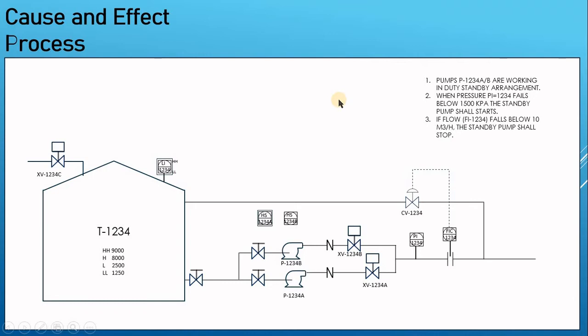We'll use this P&ID in more than one video because we'll try to add and subtract from it. The P&ID has some notes: you have a tank — assume it's a water tank — and you have two pumps, 200% meaning one is working and the other is standby. There is a valve in front of each one of them, a pressure indicator, and an FIC. The process guy said if the pressure is low, meaning users are demanding more flow and the pump cannot deliver, the pressure goes down. If this happens, the standby pump kicks in and starts — of course there is a startup procedure for the pump, but we are not talking about that now.